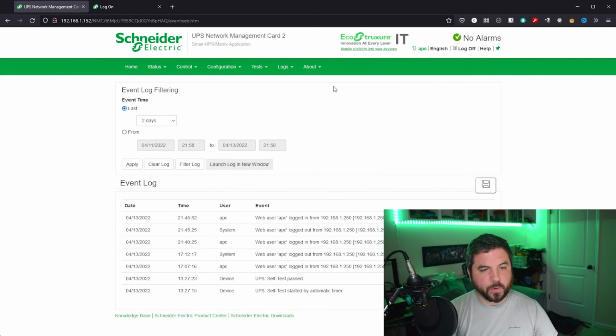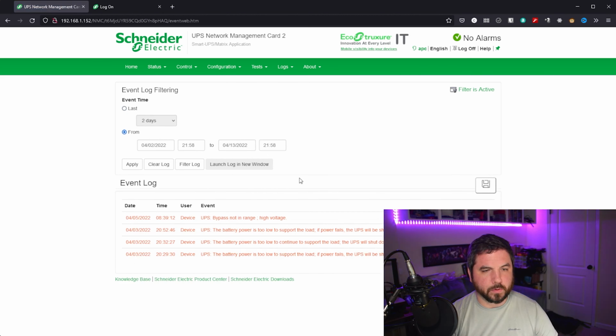And here we can see where we have some events. You would also want to filter on critical events for a power loss. So actually on April 5th, I had a power loss and it said high voltage. This is because we had a thunderstorm and it fluctuated. The power actually lost power in the entire house momentarily and everything came back on, thankfully. But because of the long runtime of the UPS, I would have been able to shut everything down with plenty of time to spare.